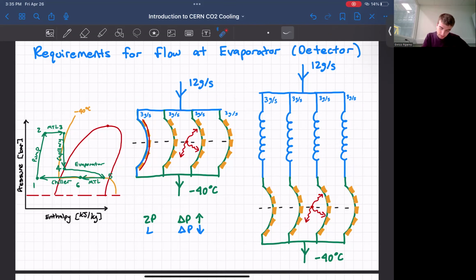So in this loop, we are liquid, and as a result the pressure drop is lower. The flow will redistribute, and of course I'm exaggerating, but it might redistribute as such. These evaporators will no longer be cooled efficiently to minus 40, and these temperatures will rise. As a result of low flow speeds, these further evaporators would break as a consequence of the single evaporator breaking.